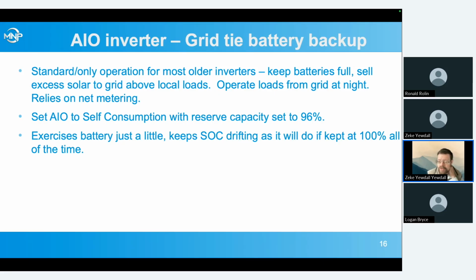So you can be drawing a little bit of power overnight, and none of the BMSs will record that. They'll still say the next morning, I'm still at 100%, when they're really not. They might have gone down to 99 overnight. The next night goes down to 98. You keep that up for 2 or 3 months, and all of a sudden you've got a battery that the BMS thinks has been kept at 100% because it's never seen a big current come out of it, but it's not. It could be significantly less than 100%.